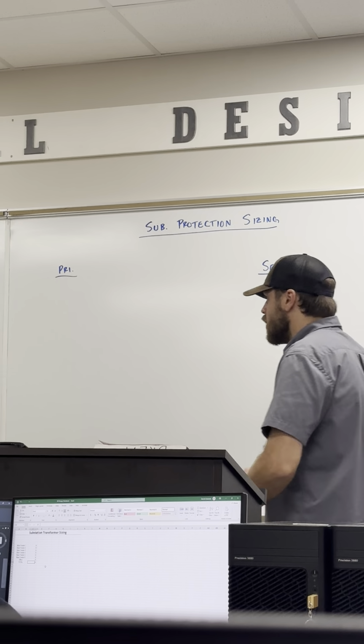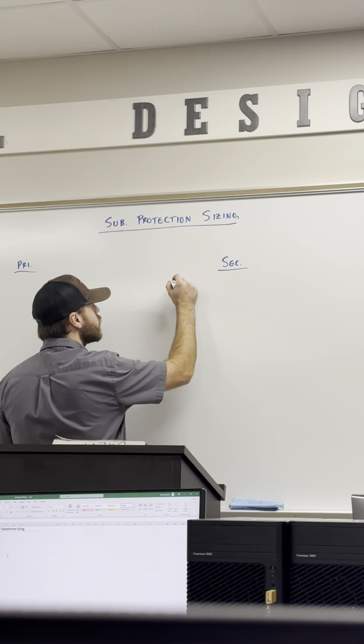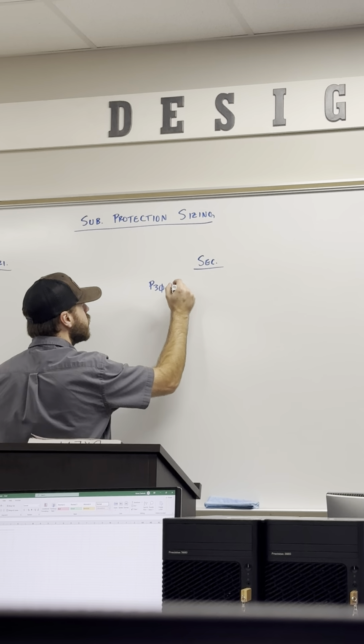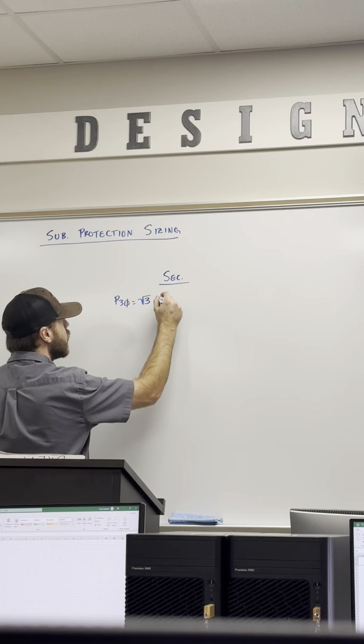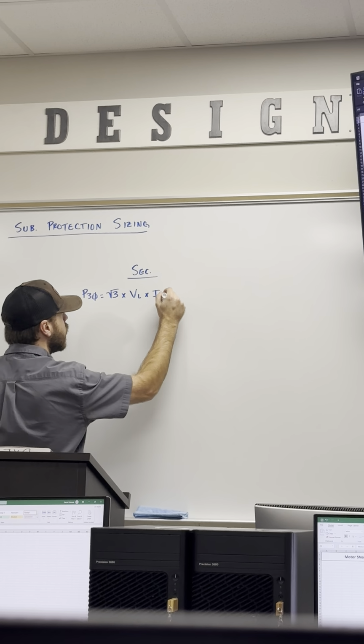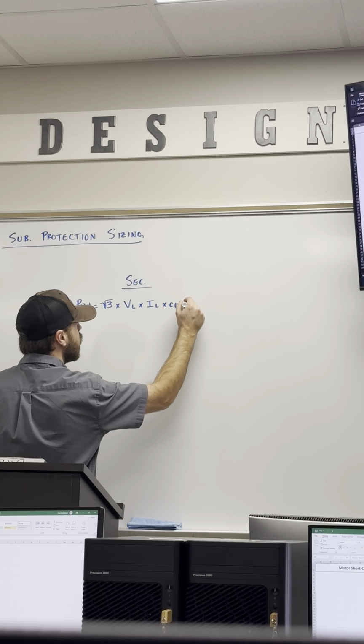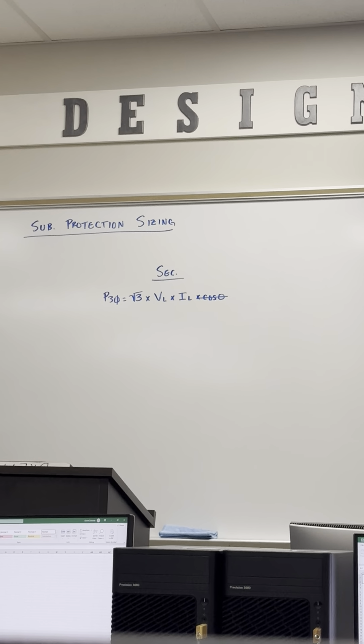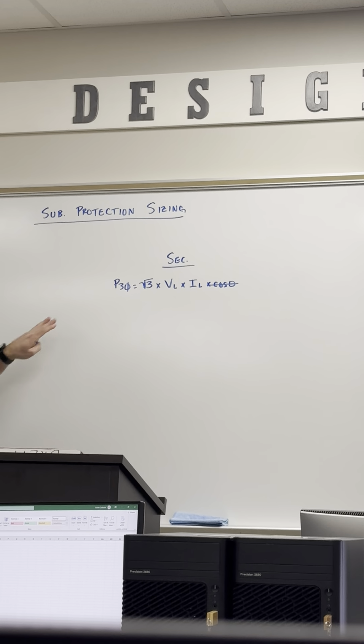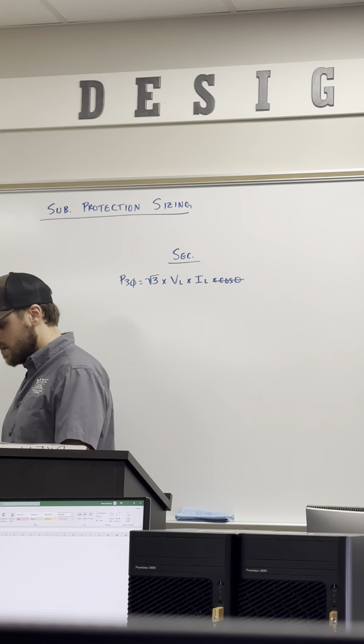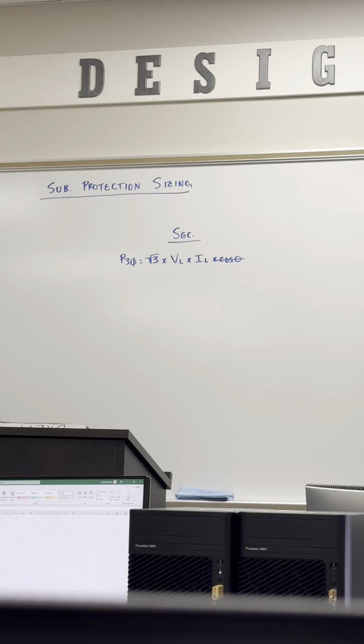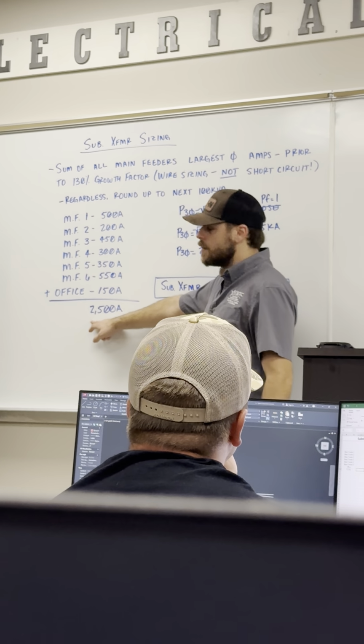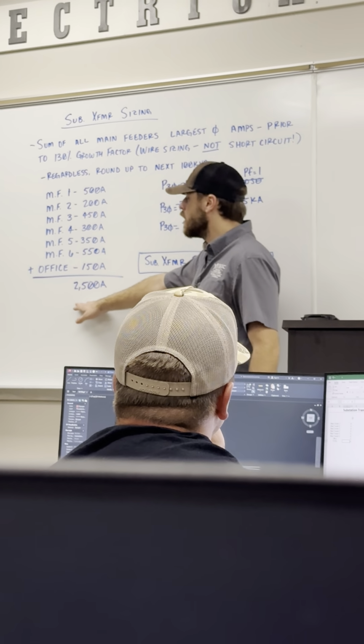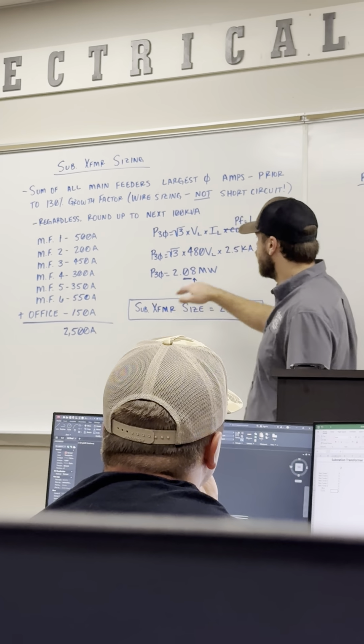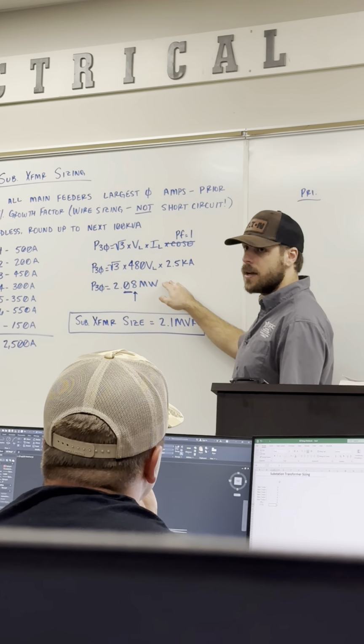So we're still going to use these three-phase equations. So we're still going to have power three-phase is equal to square root of 3 times V line times I line. And of course that cosine of theta, which we're going to end up just kind of dropping off anyways. Now, the reason we're using this formula is because we now have to solve for currents. So we can't just use this 2.5 kiloamps that we added up here earlier, because that 2.5 kiloamps would be a transformer rated current for a 2.08 MVA transformer.